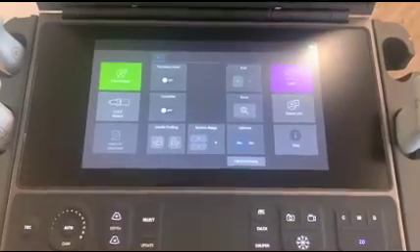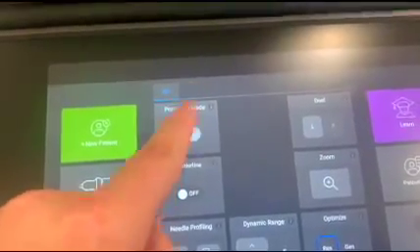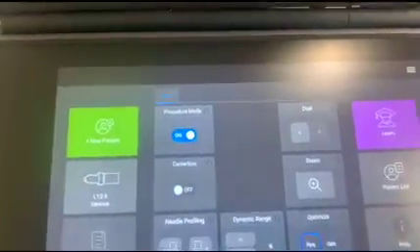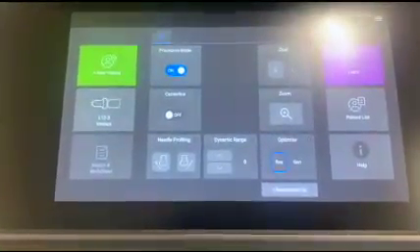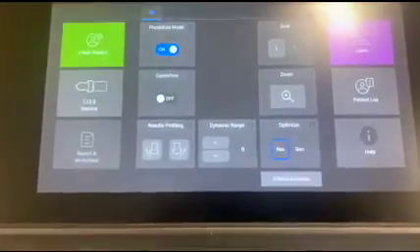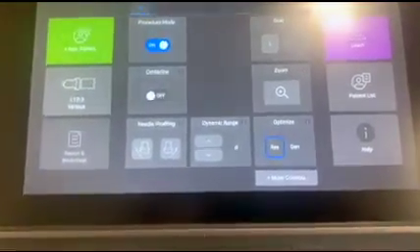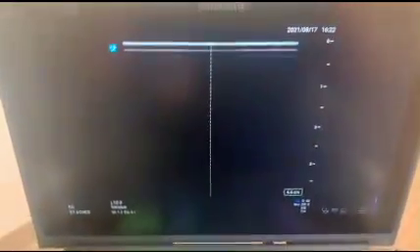There's a few cool features you should know when using the linear probe. If we go here, we can see procedure mode. If you click it, the machine will not go to sleep or turn off during your procedure. If you like using a centerline for orientation, there's a button right here, and the centerline will pop up.